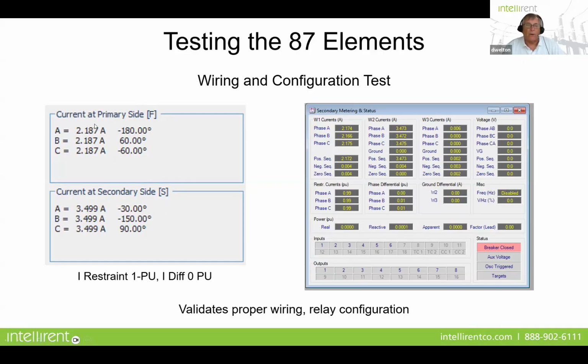So what you're going to see right here is the tap setting value on the primary side, and it's 180 degrees out. And then on your secondary side, the tap settings that are calculated there, and that minus 30 accounts for the DY1. If you don't have these phase angles properly configured in your test set, the relay is just going to trip no matter what values you put on there. All right, so what do we do here? Well, we want to validate, first of all, that we have the test set wired properly to the relay. And then we want to make sure that it's configured properly.